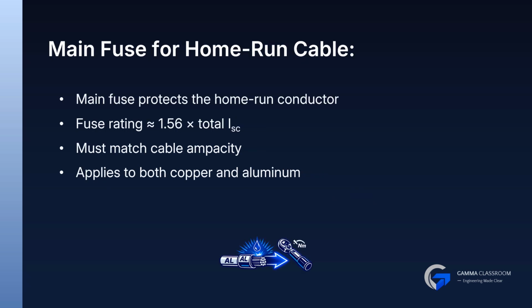The main fuse in the combiner protects the home run cable itself. Its rating is typically around 1.56 times the total short-circuit current of all strings. This fuse must be coordinated with the actual ampacity of the home run conductor, whether copper or aluminum.